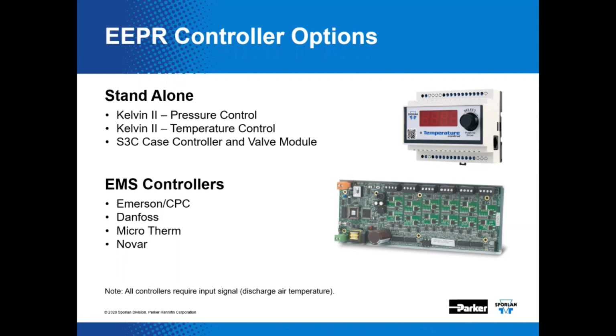More commonly, EEPRs are controlled by dedicated boards or case controls that communicate with the store's energy management system or the building automation system. This allows the technician to see and monitor case temperature, valve position, and a whole host of other things. This can take place from the controller or even from a remote location.